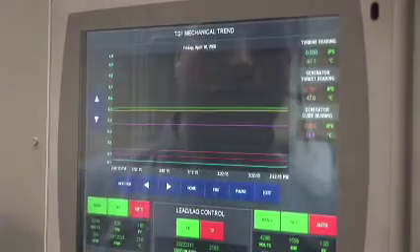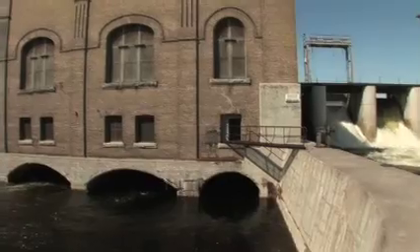Its main feature is its flexibility, and it has a lot of characteristics that make it very, very valuable — in fact critical for system operation. It's extremely fast-acting; it can be loaded up and down very quickly, much more quickly than any other generators. The water can be stored, so it can be used at the time that makes it most valuable. It can start and stop on a dime. It can start after a blackout and be used to restore the system, as was the case back in 2003.